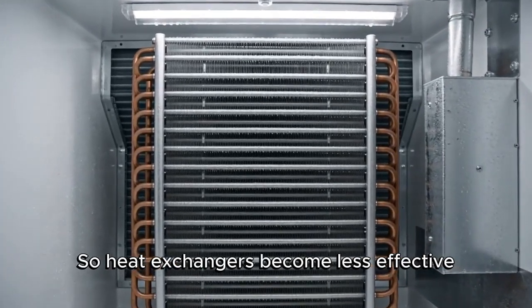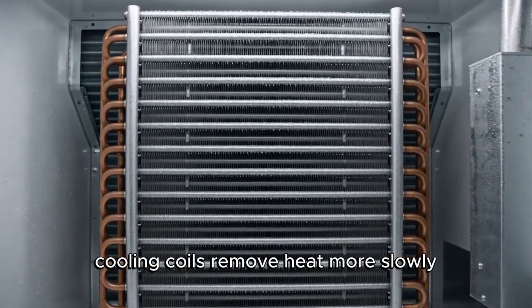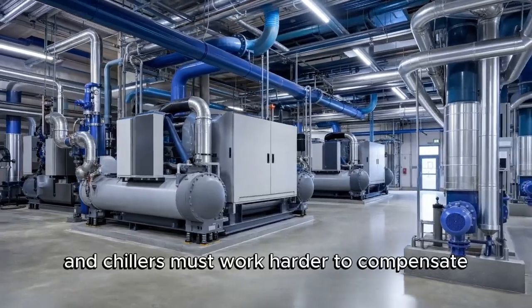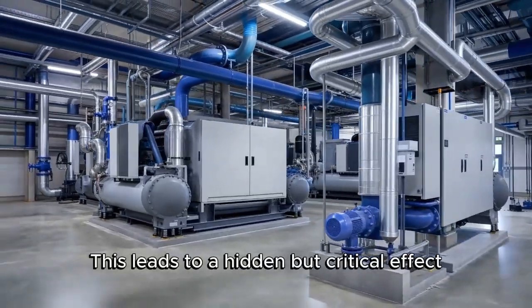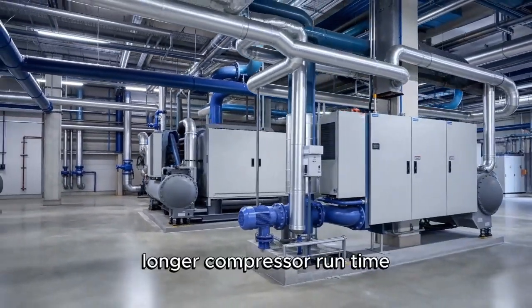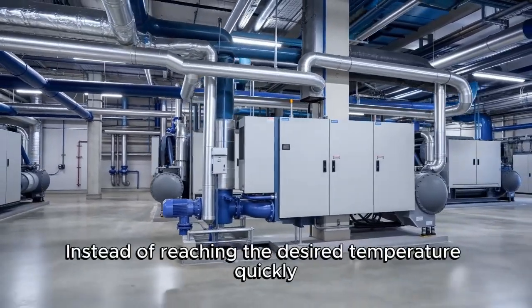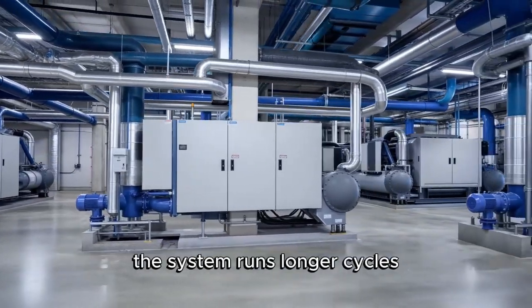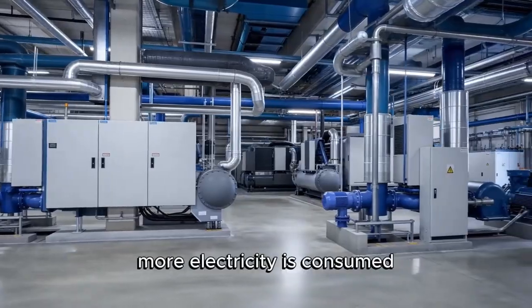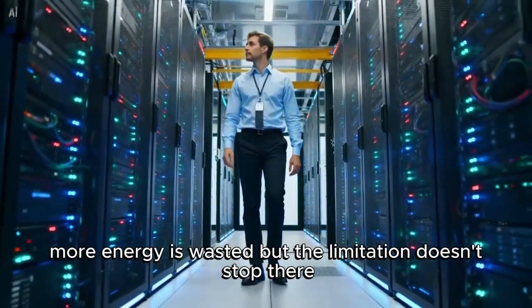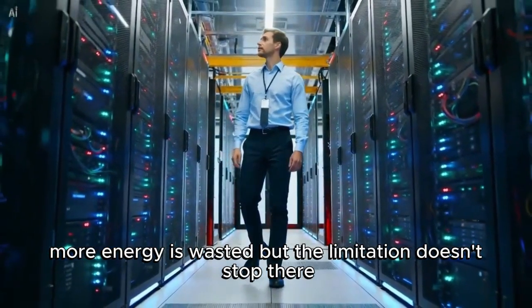So heat exchangers become less effective. Cooling coils remove heat more slowly, and chillers must work harder to compensate. This leads to a hidden but critical effect: longer compressor runtime. Instead of reaching the desired temperature quickly, the system runs longer cycles. More electricity is consumed, more energy is wasted. But the limitation doesn't stop there.